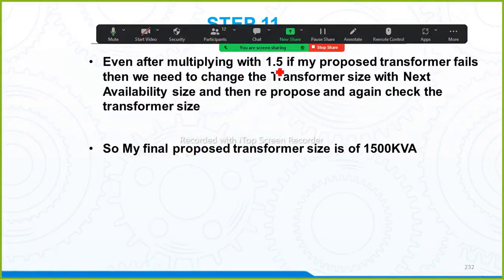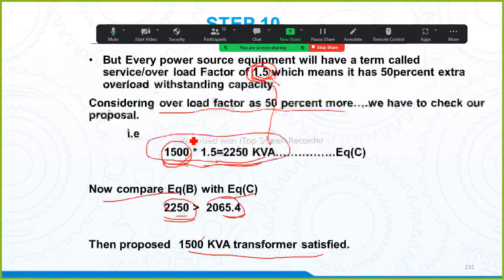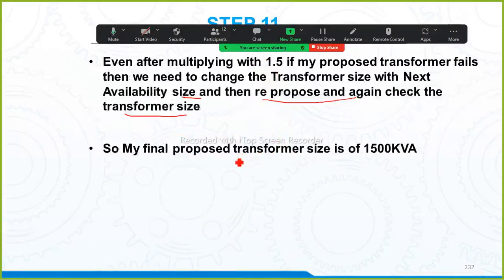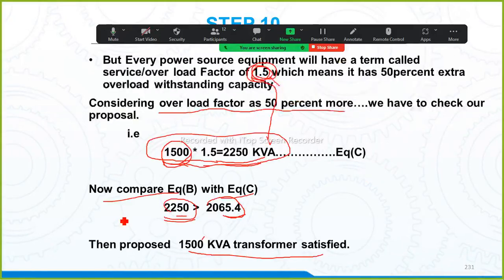But even after multiplying with 1.5, if my proposed transformer fails, then we need to change the transformer size with the next availability size, and then we need to repropose again, and we need to check the transformer size. So अगर क्या बोल रहा है? If it is not satisfied, 2250 it is not satisfied, तो अपन को क्या करना है? We need to change the next availability size of the transformer. So 2250, 1500 के बाद में next availability क्या है? 2000. So we need to check with 2000 and what is the size availability, then we need to check that. Am I clear here?